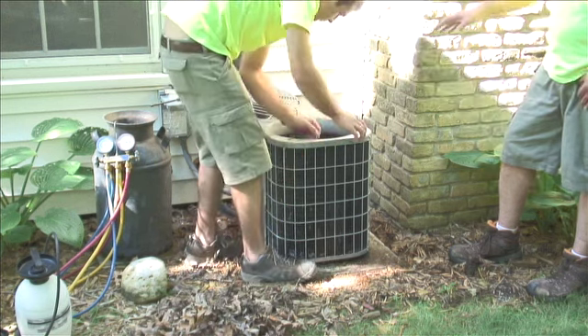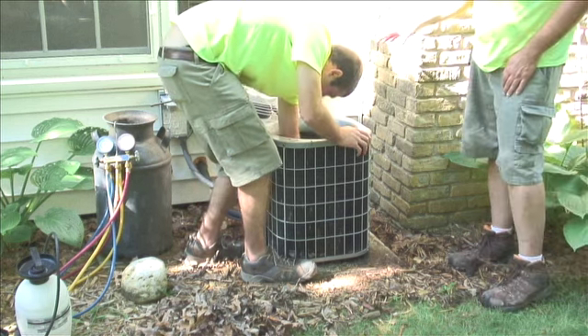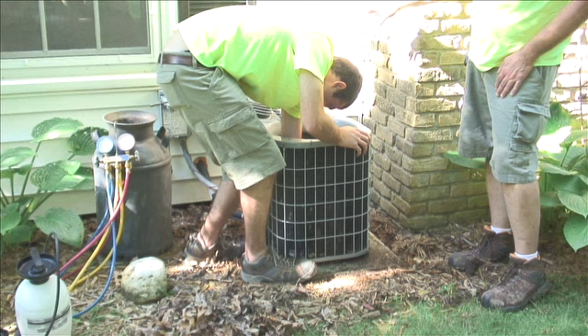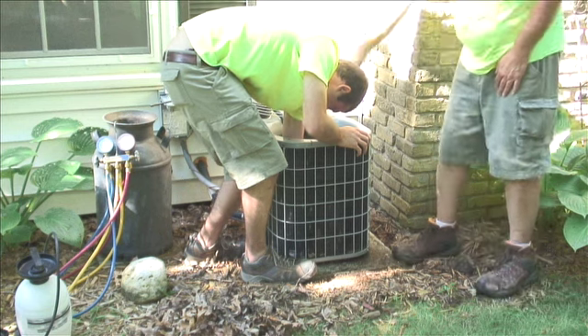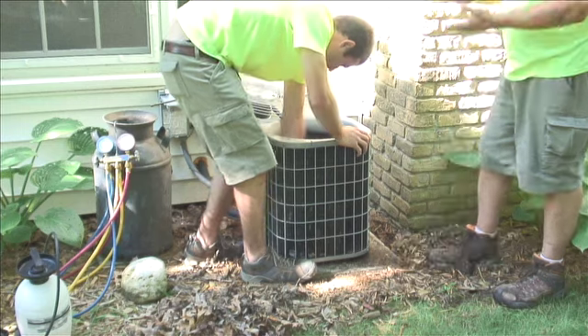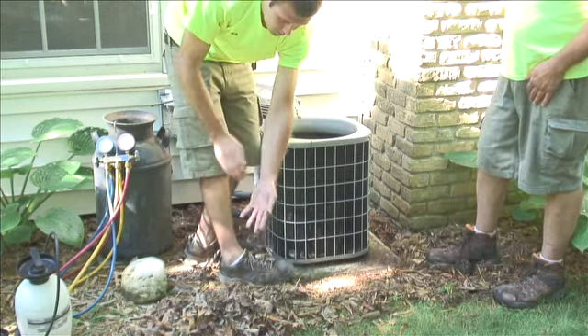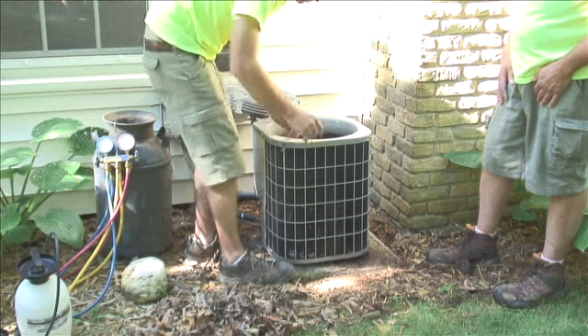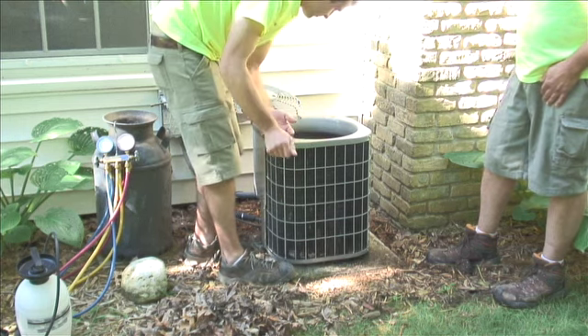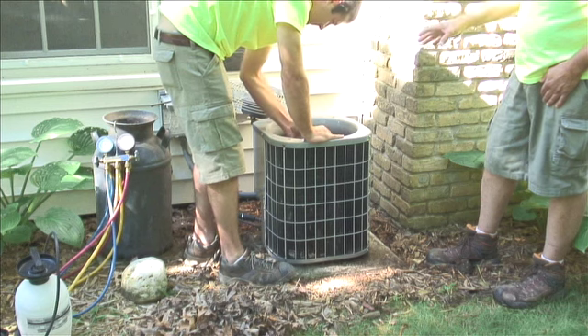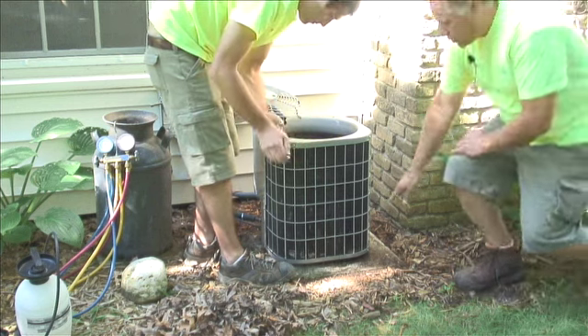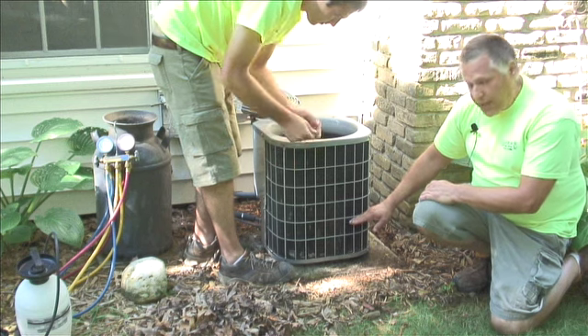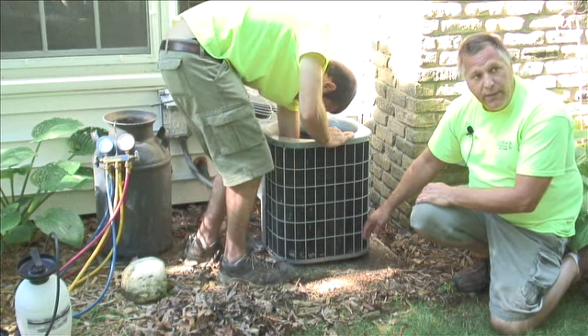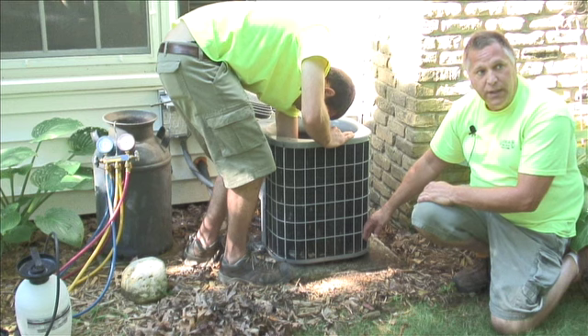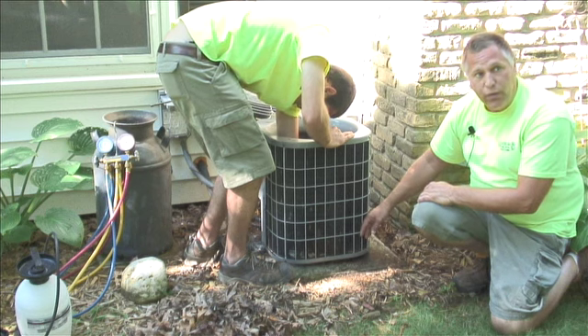A good idea, just so it doesn't build up with a lot of leaves inside, is to at least put a board over the top fan part here in the wintertime with a brick on it to stop a lot of the leaves and sticks falling from the trees inside the unit. Wrapping is okay. Air conditioners are weatherproof, but if you wrap them, you have to make sure you leave at least a 6-inch air gap around the bottom so it can breathe in the wintertime and does not get rusty and hold moisture and mildew inside it over the winter.